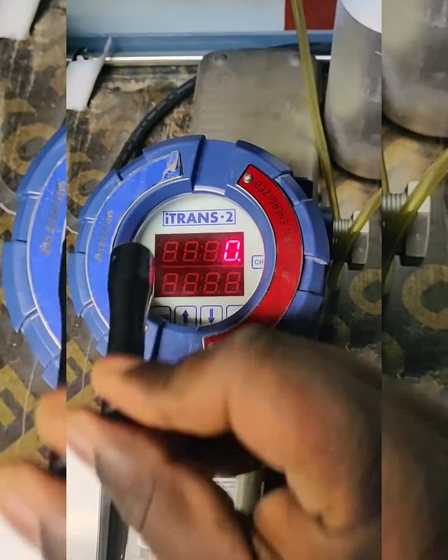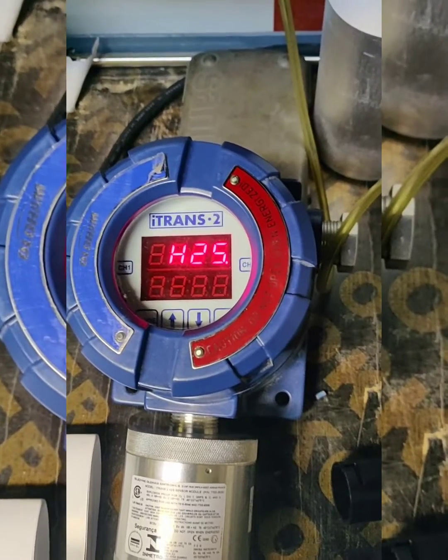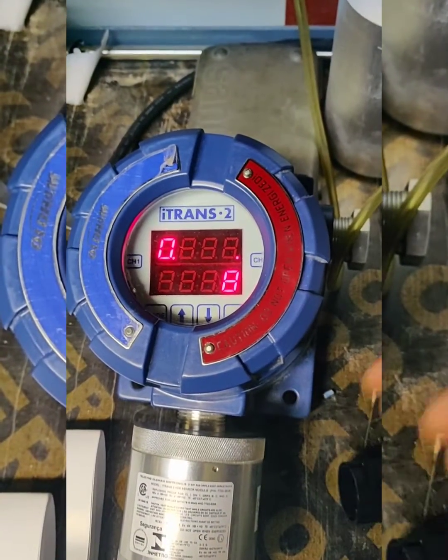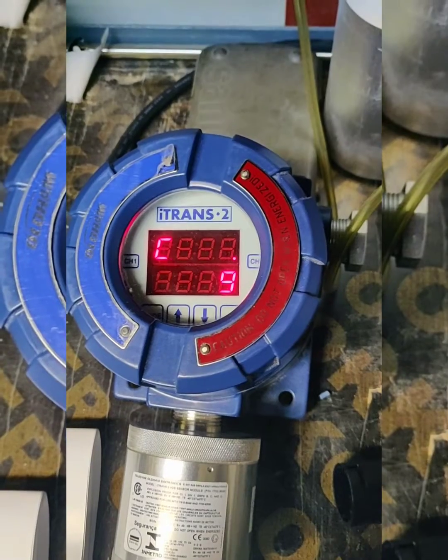Place the magnet key into channel 1. It shows the sensor type here — the sensor type is H2S sensor. Again, place the magnet key into CH1. It shows zero. For the calibration, press CH1 again.